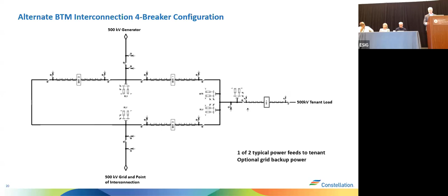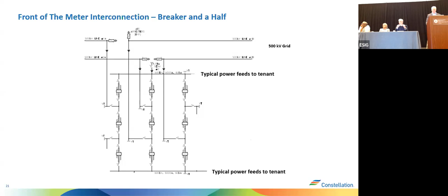And then another example of the type of interconnections that we do, based on some of the different specifics that the customer asks for. This is what's called a 1.5 design, where you have a fully front of the meter connection at the top of the drawing. 500 kV feeds, independent power feeds, come into a 9-breaker ring bus type of configuration, which provides highly reliable power to the customer. In any case where one of the tie lines goes out of service, the customer is still fed fully by power from the remaining in-service tie line.